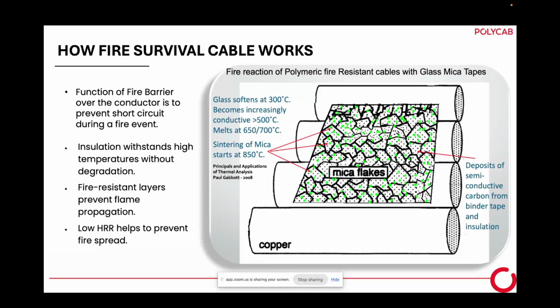But it melts at 650 to 700 degrees temperature, and the moment it melts, some carbon particles form, and these carbon particles are semiconducting material. Then it creates a problem if we use glass fiber tape or glass tape in the fire survival cable as a barrier. Many people are doing this, but it has a disadvantage: when it burns at 700 degrees, it forms carbon particles which are semiconducting, and then a short circuit takes place at higher temperature.